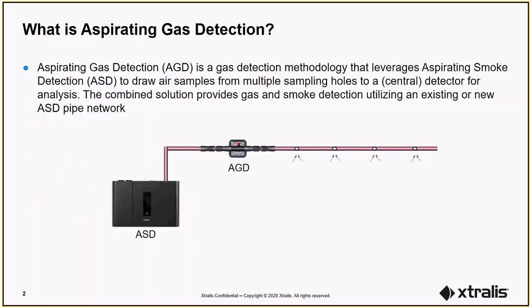Before understanding aspirated gas detection, let's start with a brief overview of aspirating smoke detection. An aspirating smoke detection system comprises a smoke detector with a fan that draws air through a network of pipes to the detector for analysis of smoke. Pipe networks are extremely flexible in their deployment, can extend for hundreds of meters, and comprise sampling holes strategically positioned in a protected space to actively draw in smoke particles.